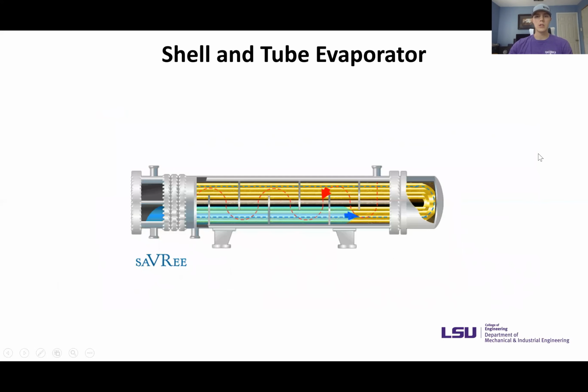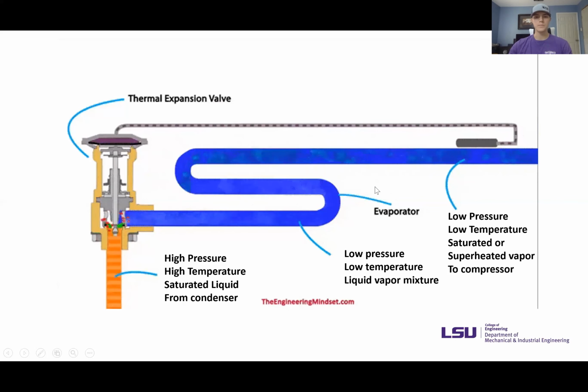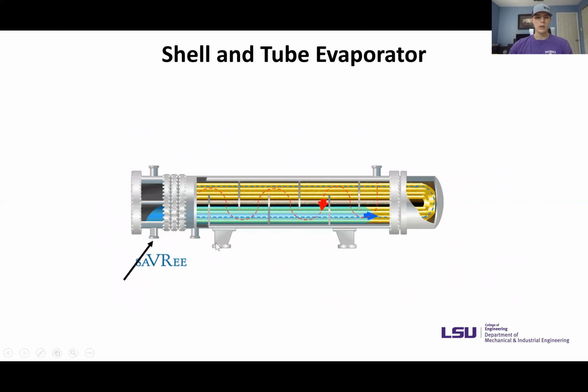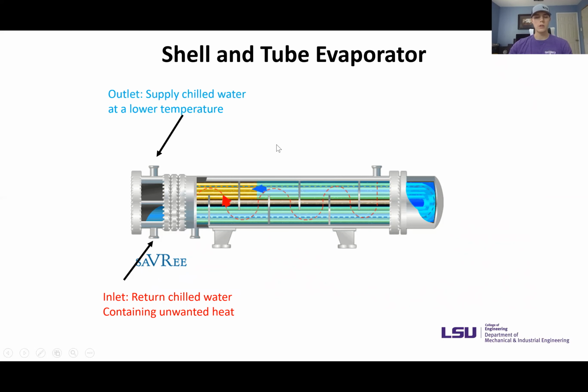Here we can see the shell and tube evaporator. Now this is what you would find previously in the evaporator right here. So as you have in the inlet, you'll have the return chilled water containing the unwanted heat that was collected from the building.